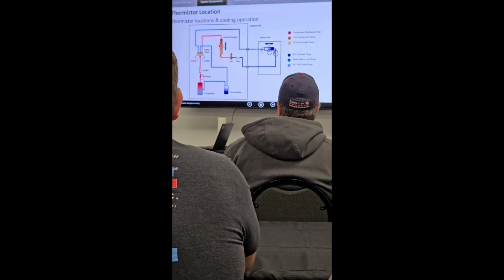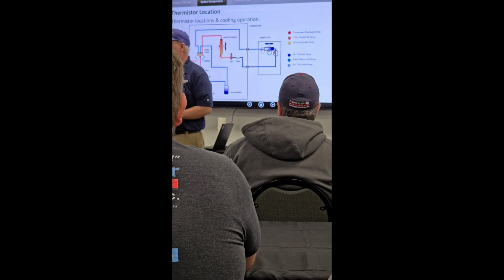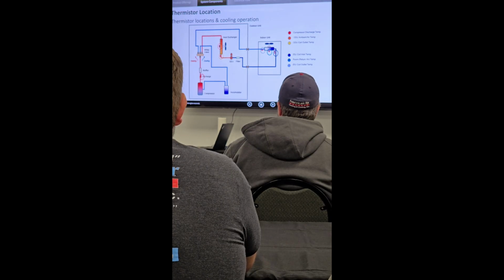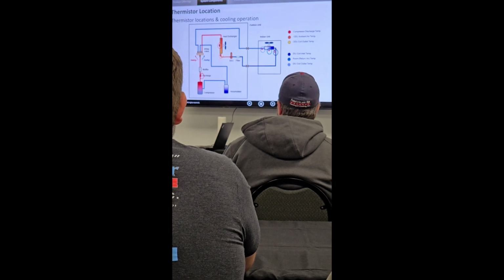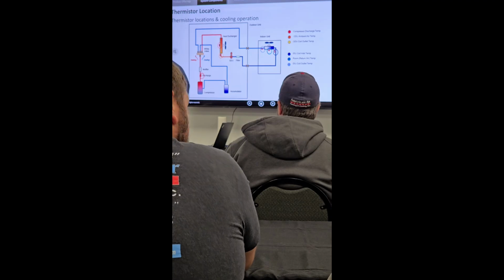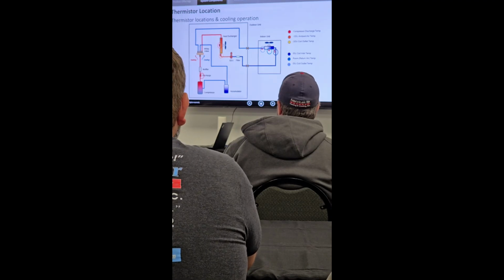It's not really the vibration of the compressor causing that, because there's very little vibration in that compressor, it's the movement of the refrigerant causing the movement. I had a Samsung 3-ton with the two fan motors. Yes sir, so it looks like I might make a trip back in. I would, because what happens is it becomes an oil trap, and that becomes an issue for you later on. As long as it's one loop, you're fine.